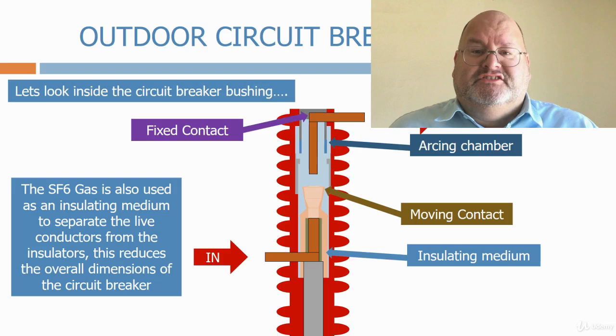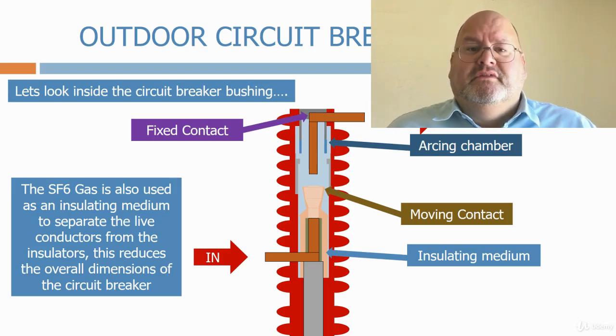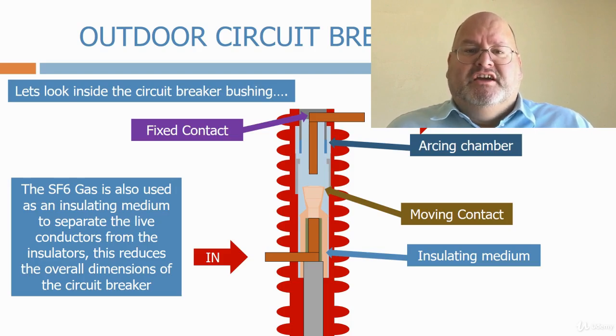The high voltage SF6 circuit breaker is a very advanced design, and it's quite simple in its operation compared to the earlier circuit breaker types that we used to use. It relies on the fact that the dielectric strength of SF6 increases as it becomes pressurized. The shape of the gas chamber inlets are designed so that as the circuit breaker mechanism opens the contact, it also compresses the SF6 gas as it enters the circuit breaker chamber. This creates a high-pressure SF6 zone inside the chamber, which prevents the restriking voltage bridging the contacts.